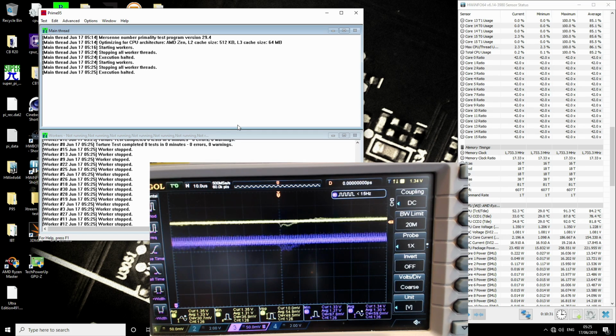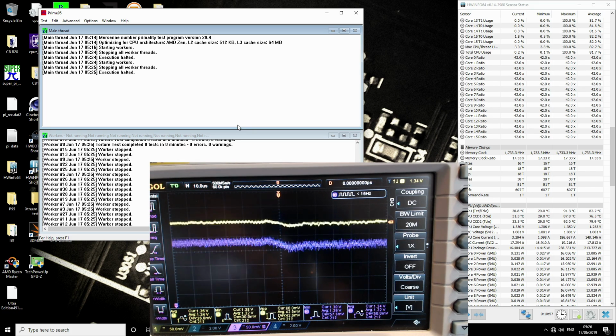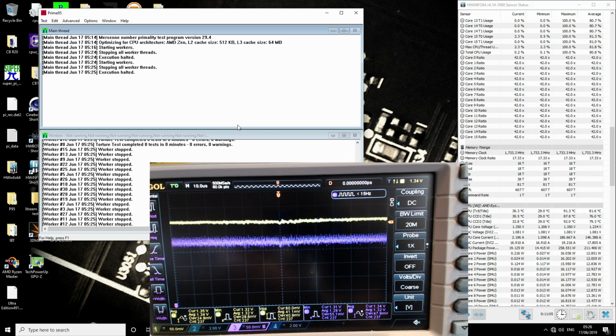What you should start with is... because basically, if you raise the average voltage, the minimum voltage goes up with it. So you can't compare 1.35 level 6 versus 1.35 level 1, because 1.35 level 1 is going to have an average voltage of 1.35, and therefore the undershoot is going to be pushed up by almost 150 millivolts. Not really, but the undershoot gets worse the more current you have flowing through the system, so the higher the voltage, the more current there is to cause the undershoot and overshoot.